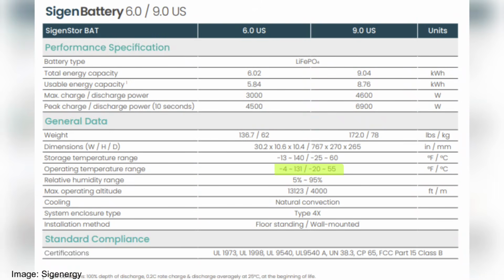The battery falls within the industry standard operating temperature ranges from -4 degrees Fahrenheit up to 131 degrees Fahrenheit. But where it outperforms other competition is it has a maximum altitude of 13,123 feet, meaning it can go pretty much anywhere within the continental United States. From a power perspective, it has a 3,000 watt discharge from the 6 kilowatt hour battery and a 4,600 from the 9 kilowatt hour battery. Now that stacks as you add multiple batteries, but ultimately the inverter caps the max output per stack at 11.5 kilowatts out, or about 48 amps. Now, of course, for that peak startup power, it can go up to 17.1 kilowatts in a 10-second burst, which means you could get over 70 amps, which is enough to start most of the large loads that would be inside a house like an AC unit if you're in backup capacity.